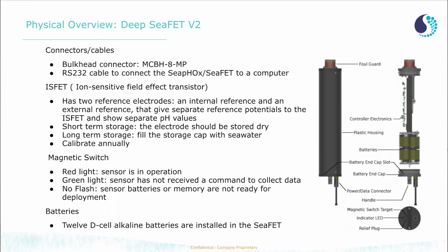For short-term storage, we recommend that you store the electrode dry. However, for long-term storage, we recommend that you use filtered, pure seawater. It's also generally recommended for all of our products, including the SeaFET V2 and Deep SeapHOx V2, that you calibrate the system annually.